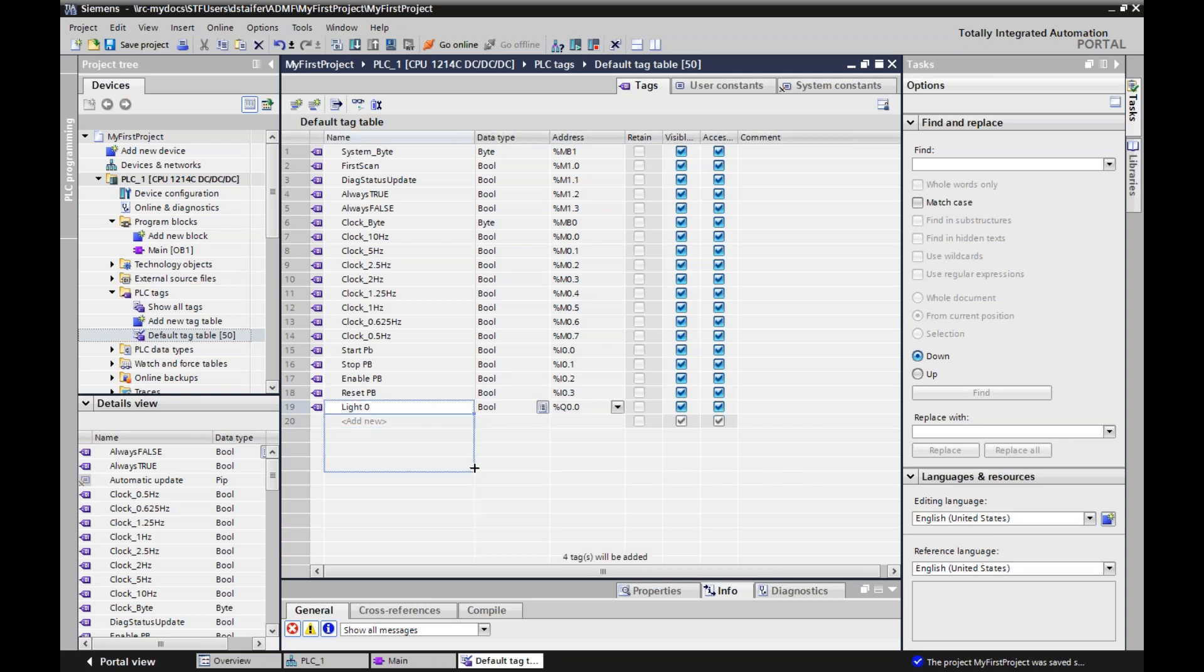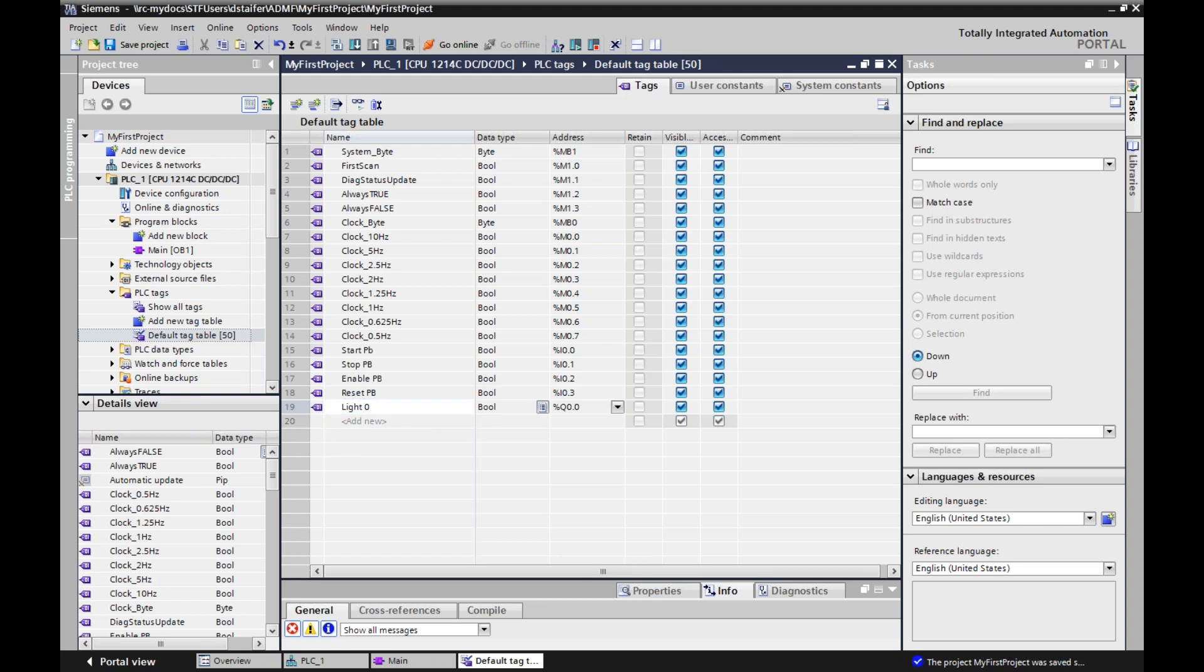So now I'll move to my outputs. So light 1. Now that went to the input, but all you do is hit the little arrow, change it to a Q.0. Boom. There we go. And just for confusion's sake, I'm going to change this to light 0 just so we start numbering 0. And if I've got a bunch of lights, I can copy and paste. And I think it did it. There it goes. One, two, three, and that way it matches. So this is where I would always start, to start my tags.